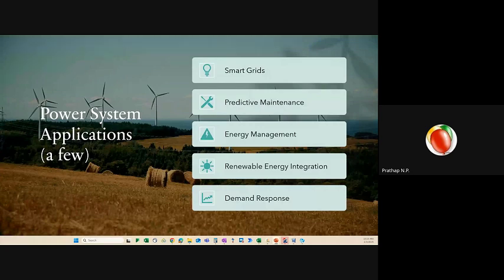So once that contact is closed, they are basically giving us permission to close, and they will call us and say, "Hey, we have an overload condition. Can you please start your generator?" And the customer would start the generator. If it's already running, they'll just issue a synchronizing command, and it will close the breaker. This term is called demand response. Based on the grid's demand, the client is responding to that. The generators are responding to that. So that's one application where communication between these devices is helping a lot.